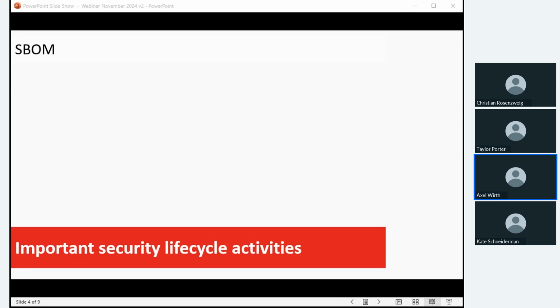Nevertheless, SBOM is a good tool here. It helps us in the pre-market to identify vulnerabilities and potential risks as we design new devices. It helps in the market approval process because we can demonstrate to regulators and notified bodies that approving authorities understand that the manufacturer has control over their vulnerability management processes via an SBOM. SBOM can also be used in the post-market so that both manufacturers and operators can continuously monitor for new vulnerabilities that come up over the life of the device. And obviously, should a software component reach the end of support, the operator can assess the risk and can take action, either through external security controls like network segregation and firewalls, or device replacement.